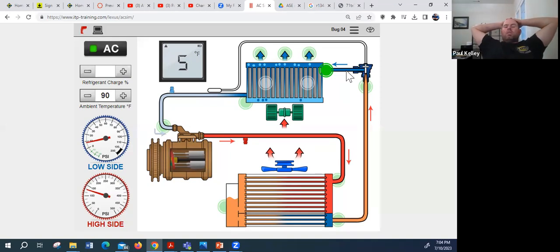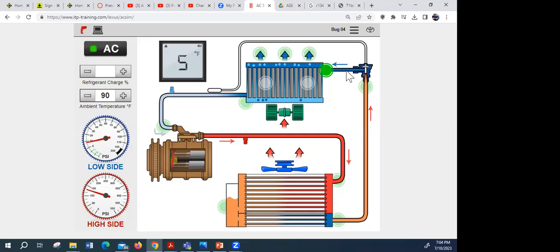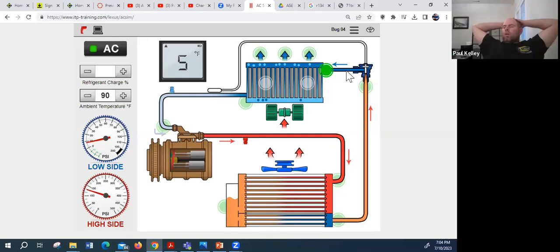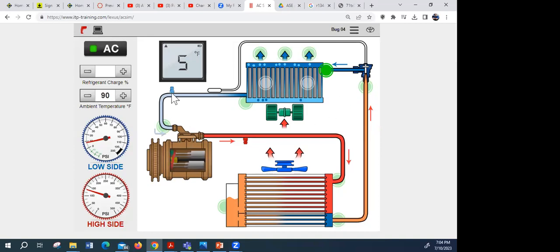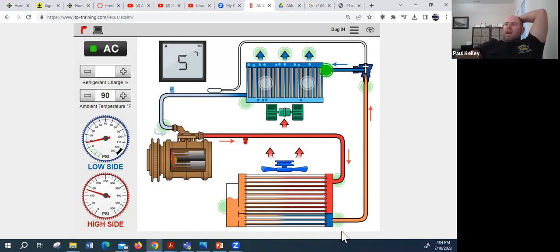Remember, temperature and pressure have that relationship. So if it's a low temperature, what is the pressure? Low, right? How would we get low right there? Because there's a restriction, so it's only letting a certain amount of refrigerant pass by. Exactly. So right here we'd have normal, and then it would actually draw into almost a vacuum. I've seen where it'll draw these into a vacuum if there's a bad restriction.